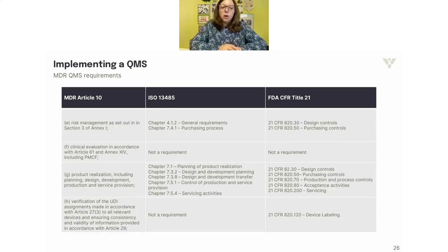Next, we have a specific call out for risk management, and the reference here is to another part of the regulation to essentially say you have to follow these requirements for risk management. From an ISO standpoint, again, we have two very different sections here. Same thing with FDA. From an FDA standpoint, they are not really calling out the requirement for risk management. And it is something that while the FDA has published quite a bit of guidance on it, there still really isn't a very clear spot in the CFR where they're telling you to have a risk management system.